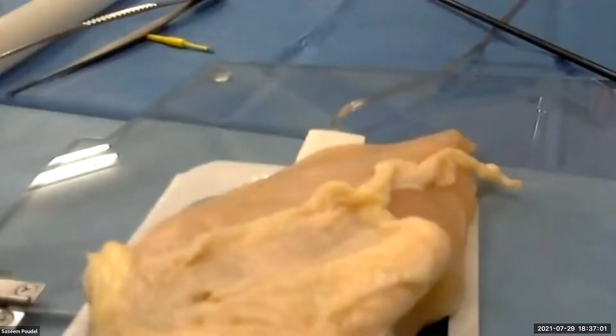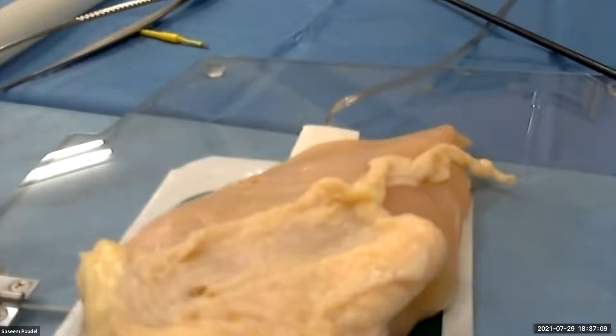So most of the new machines have a sort of fail-safe check, but older machines do not have these. If you're using earlier generation machines, you have to be very careful of where you place your dispersive electrode, and make sure that it does not get detached, because it's a second electrode. There is electricity there, and you can get burned there. Okay, that's all I have. We can go to the next one.